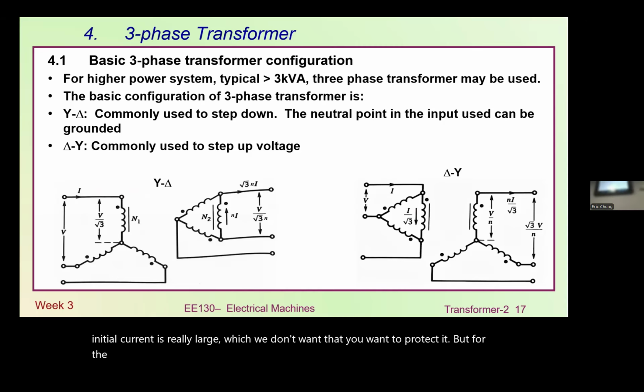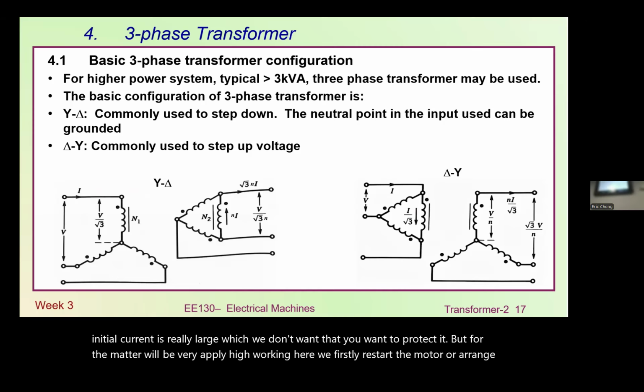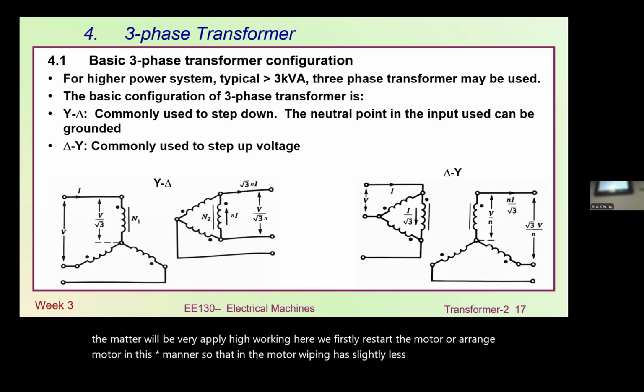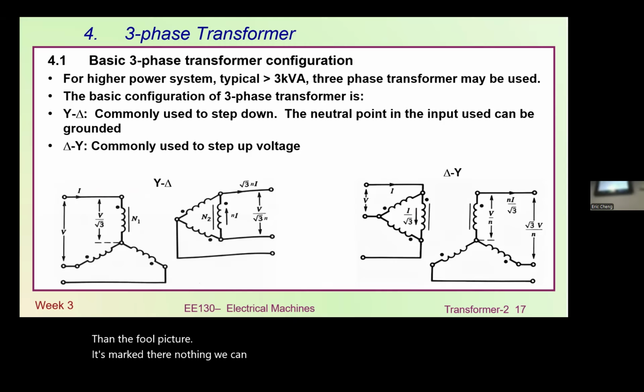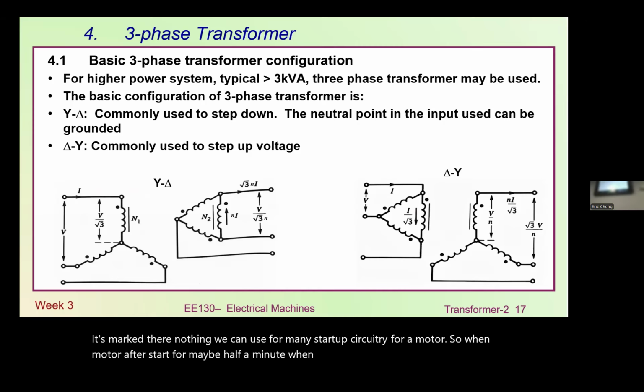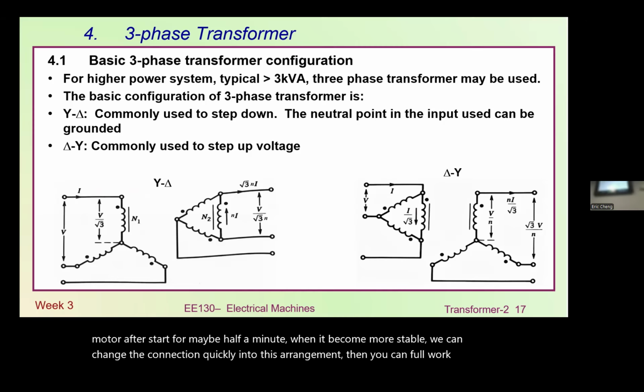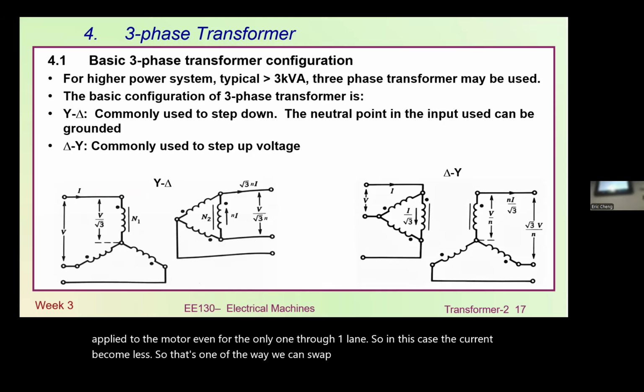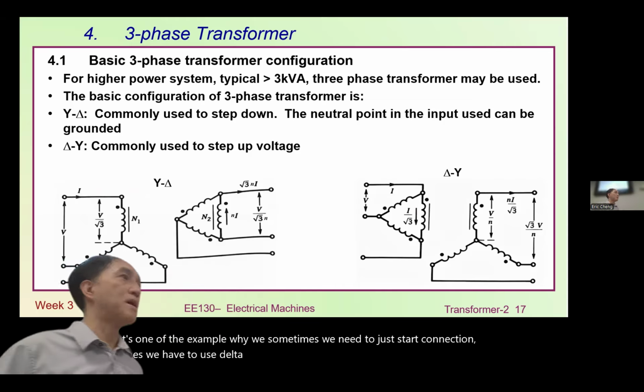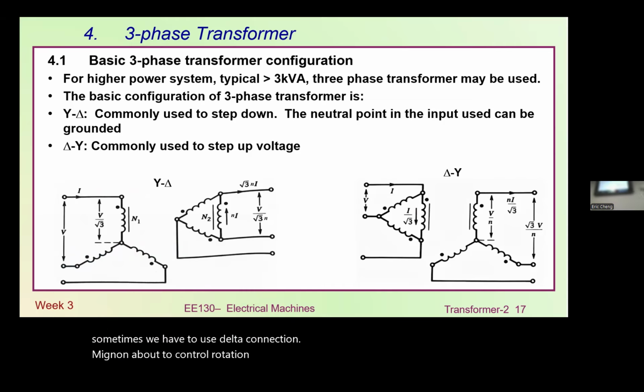One method is when you apply high voltage, we start the motor arranged in star manner, so the motor winding has slightly less voltage than the full voltage. That's one method for startup circuitry for a motor. After the motor starts, maybe after half a minute when it becomes more stable, we can quickly change the connection into the other arrangement, then you get full voltage applied to the motor. If the motor is already full running, the current becomes less. So that's one way we swap from star connection to delta connection. That's an example of why sometimes we need star connection and sometimes delta connection, mainly to control voltage and current on the electrical machine. You get that?